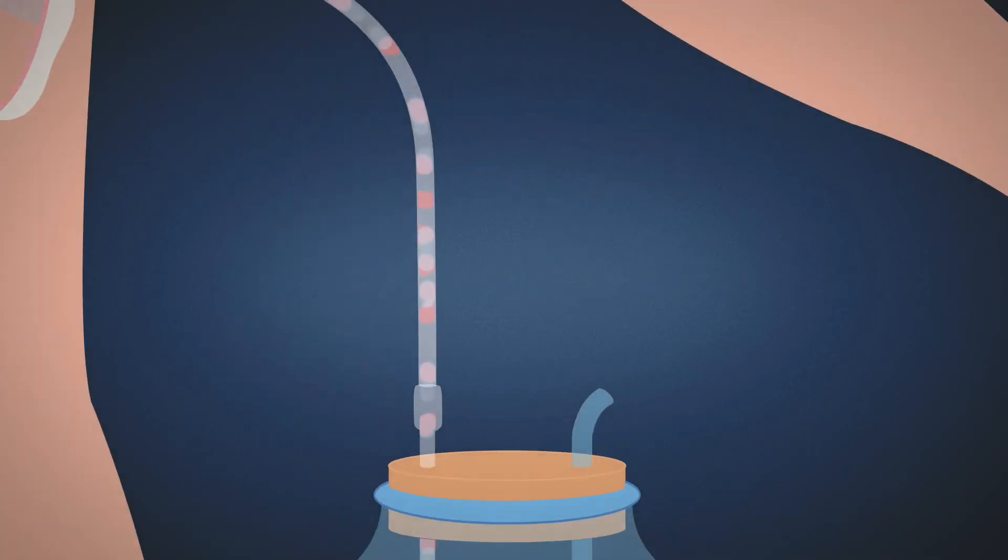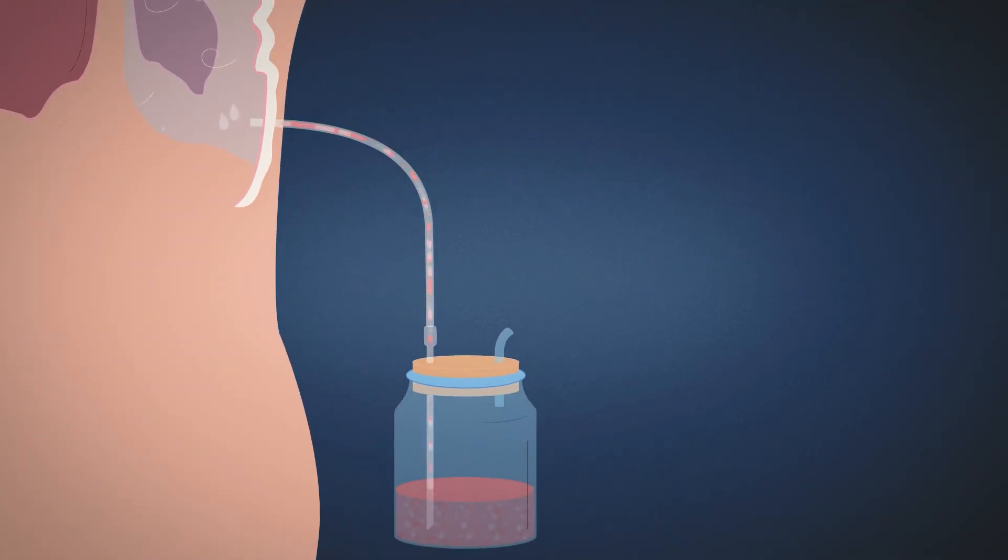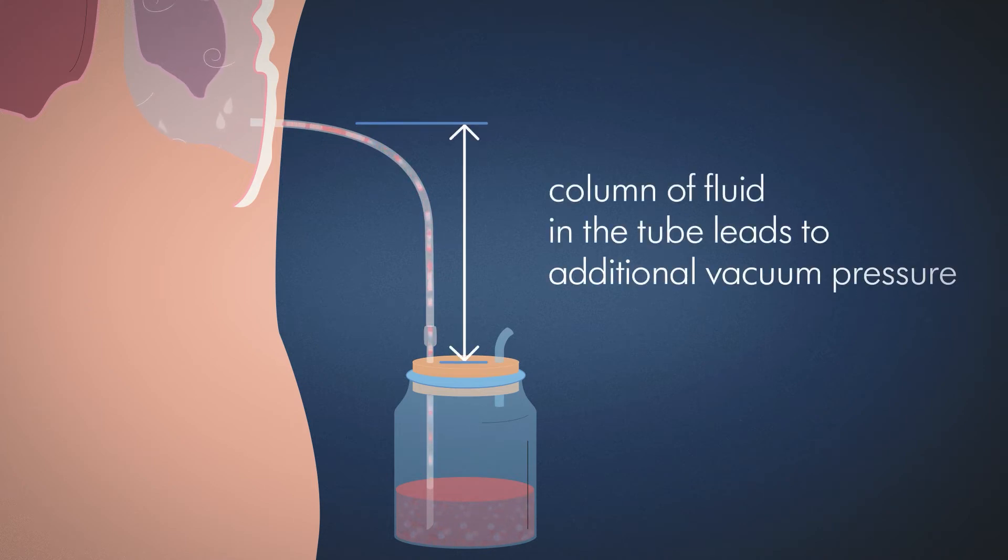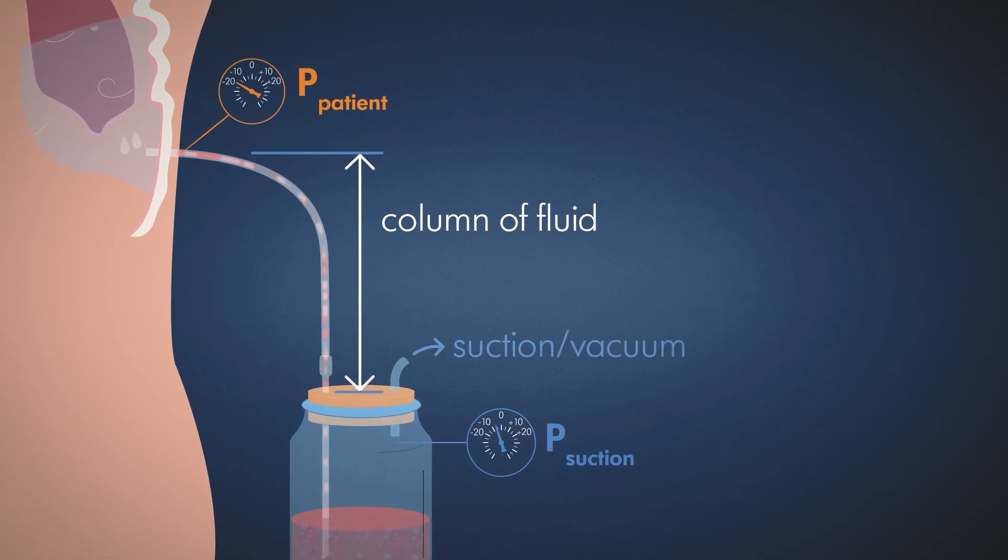If the end of the tube at the drainage container is below the level of the thorax, the column of fluid in the tube leads to additional vacuum pressure. The negative pressure applied to the patient is therefore higher than the suction level set at the thoracic drainage system.